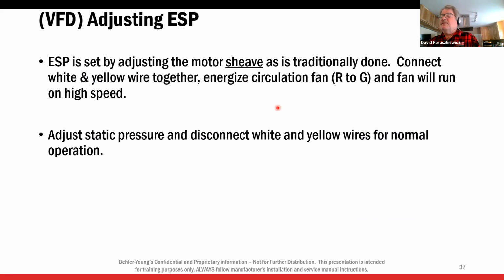All right. Before I move on, though, I want to tell you one thing real critical on both of these motors, the Axion on the little one and the VFD on the big one. They will, everybody listen really close, they will run in the correct direction no matter what. All right? If I swap a leg of L1, L2 on a 3-phase, the blower will still run in the right direction. So you cannot check blower or compressor rotation by looking at the blower. Okay, I want to be real clear. You cannot check compressor rotation by looking at the blower. The blower will run in the correct direction no matter what. So you have to put a gauge on the compressors to make sure they're running in the right direction. All right, so I want to make sure everybody's really clear on that.